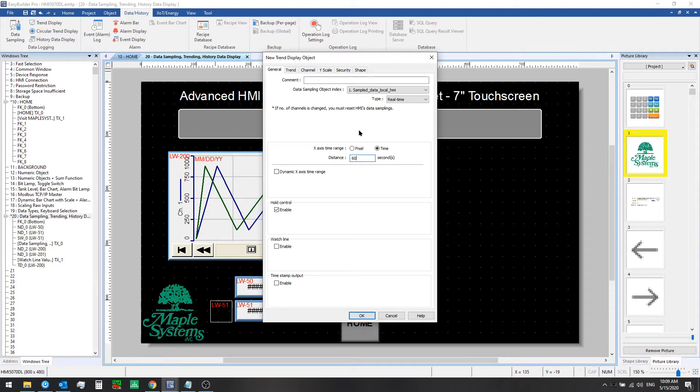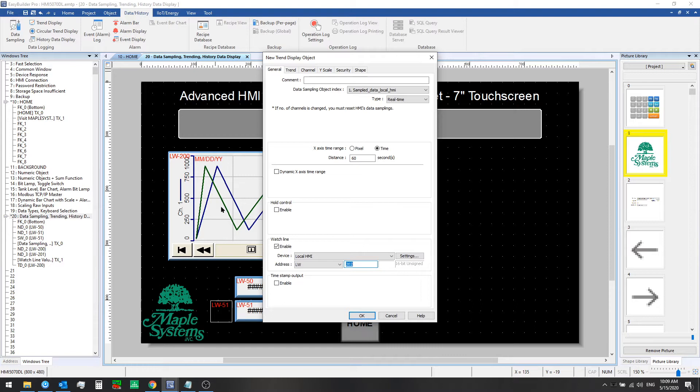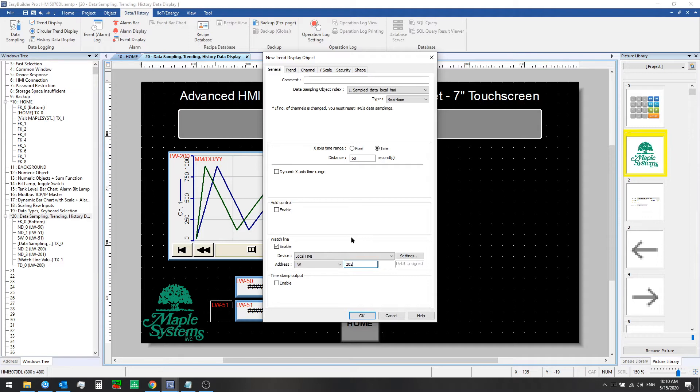So we'll use 60 seconds for this example and we'll enable the watch line feature where we can click on the chart. It will create a vertical line at that point and we can read the values from that exact point in time. Those values will be written out to the designated register, and since we're using two channels of data, the first value would be written into local word 202 and the next value will be written into local word 203.